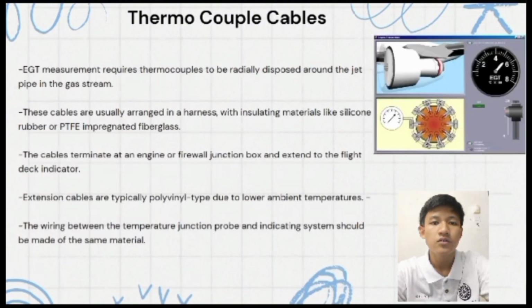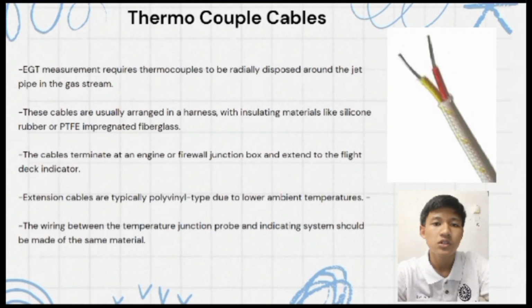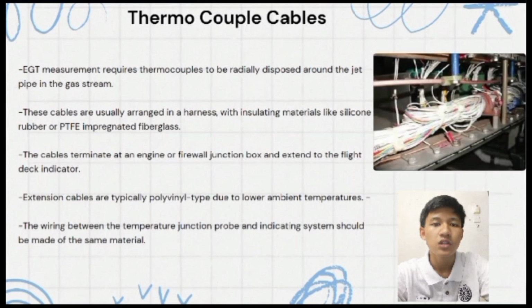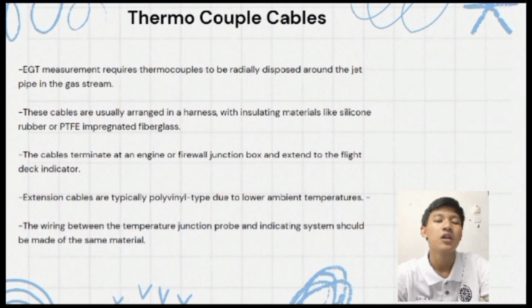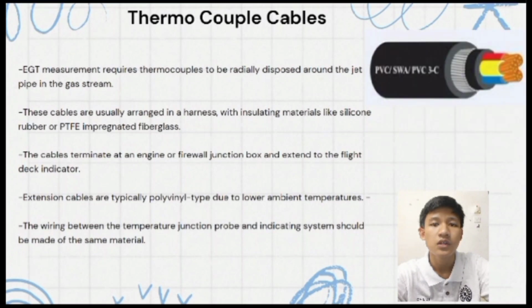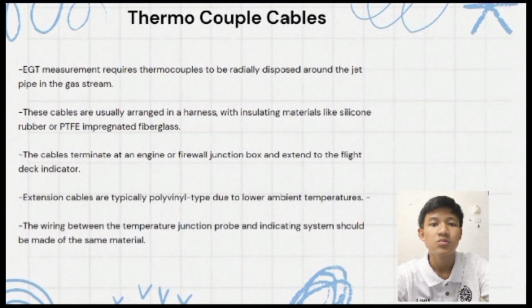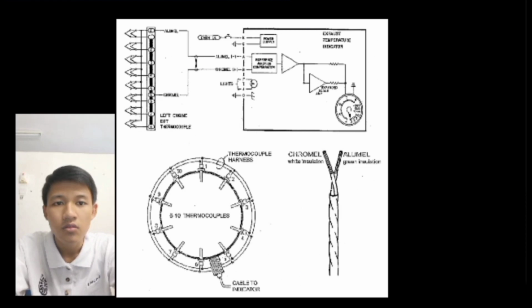EGT measurement requires thermocouples to be radially disposed around the jet pipe in the gas stream. These cables are usually arranged in a harness with insulating material like silicone rubber or PTFE impregnated fiberglass. The cable terminates at an engine or firewall junction box and extends to the flight deck indicator. Extension cables are typically polyvinyl type due to the lower ambient temperature. The wiring between the temperature junction probe and indicating system should be made of the same material. So as you can see here, this is an example of the EGT indicating system with thermocouple harness installation.